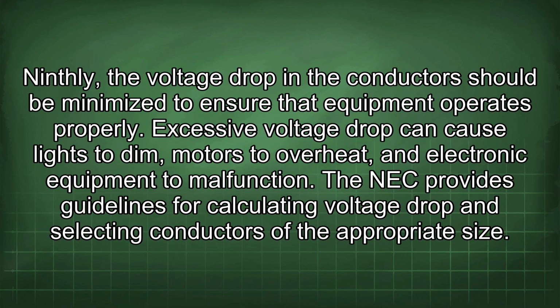Ninthly, the voltage drop in the conductors should be minimized to ensure that equipment operates properly. Excessive voltage drop can cause lights to dim, motors to overheat, and electronic equipment to malfunction. The NEC provides guidelines for calculating voltage drop and selecting conductors of the appropriate size.